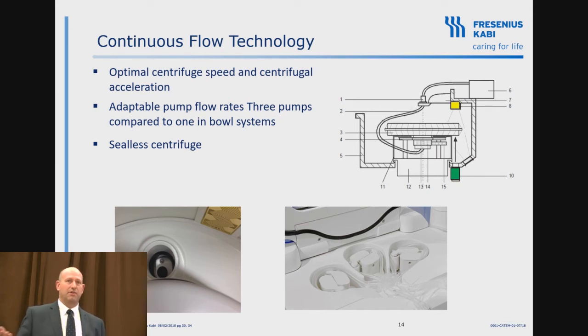So 3 minutes, we have 300 cc's. So that's pretty fast. And our product quality does not decrease at all on high speeds. I'll show you our data. We have a sealless centrifuge. Our disposables, all bonded tubing and plastic. There is no friction surfaces. And on this chamber, as there's a schematic of it, sits on top of a rotor that spins. So this rotor is spinning, and on top of the rotor, the chamber is suspended, and that spins at twice the speed.